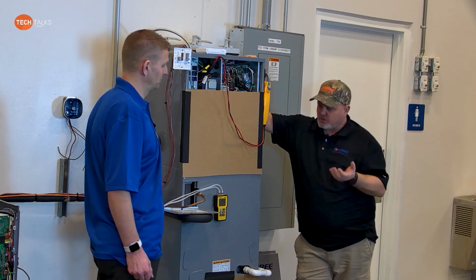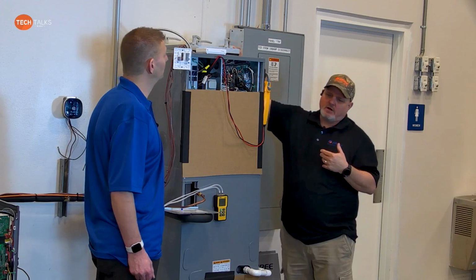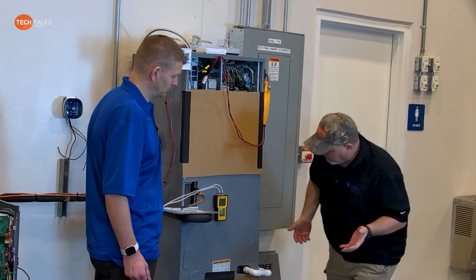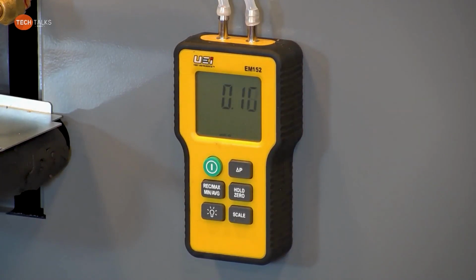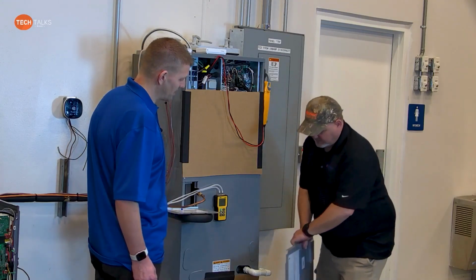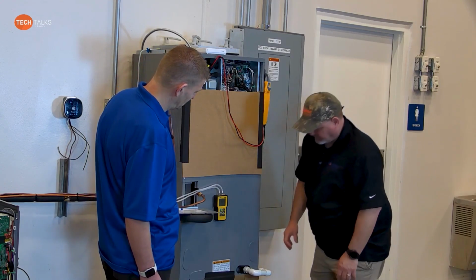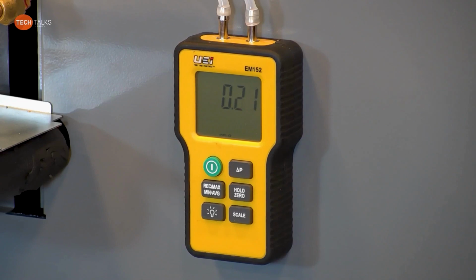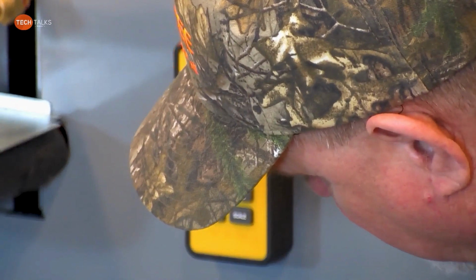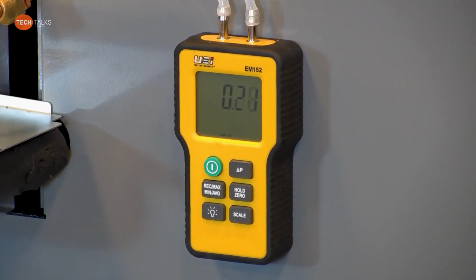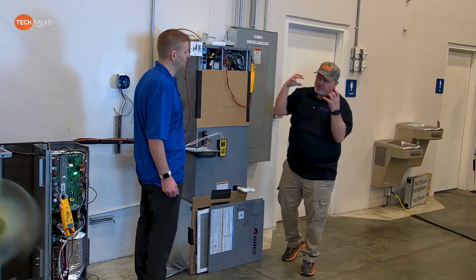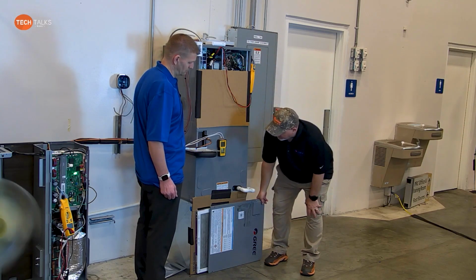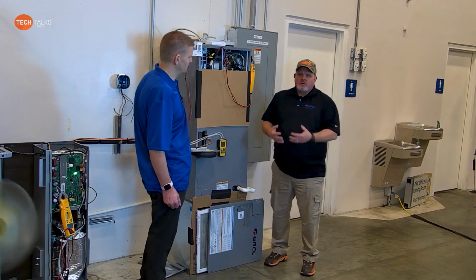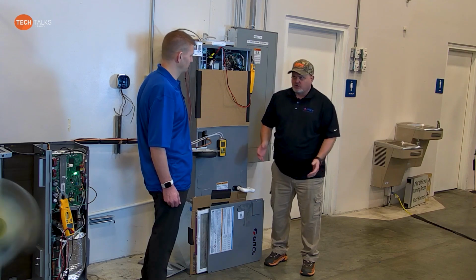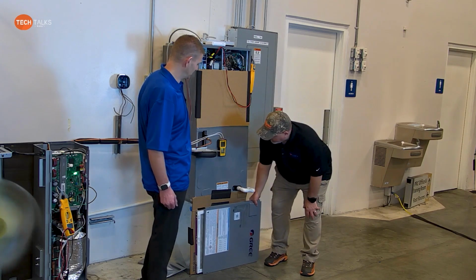So I kind of want to demonstrate what happens here. We've got something restricting our airflow on the top up here. We're only running a 0.1 total static. That's nothing. So let's have a little fun. Restrict that return. We jumped up to almost 0.2, right? Let's give it a little more. Now we're at 0.3, which is still not bad static. But again, I have no ductwork. I'm not pressurizing the system. I'm just trying to simulate here. So I'm choking it down. Basically, I'm choking the return way more than you'd ever be able to choke it if you had a completely ducted system. But it kind of gets the point across.